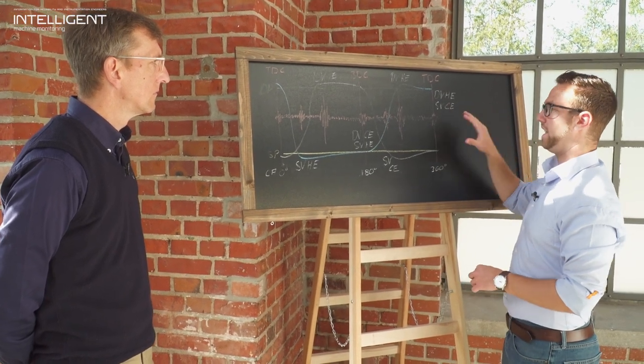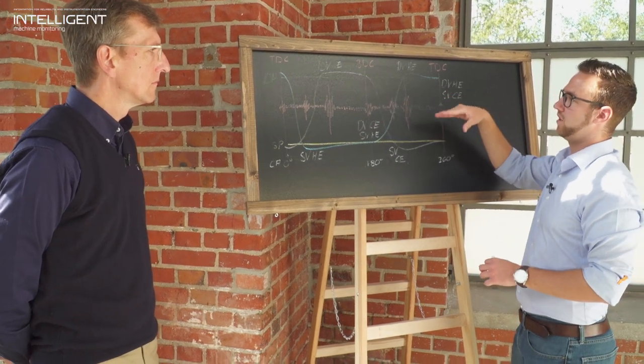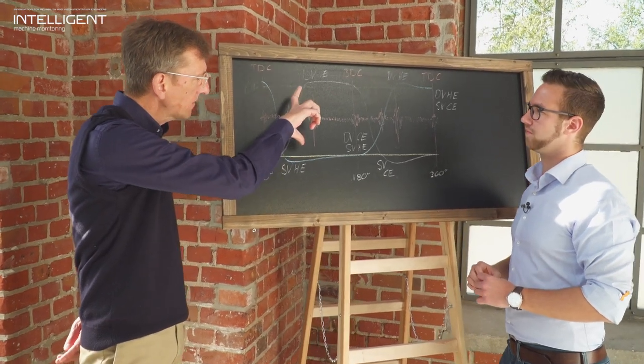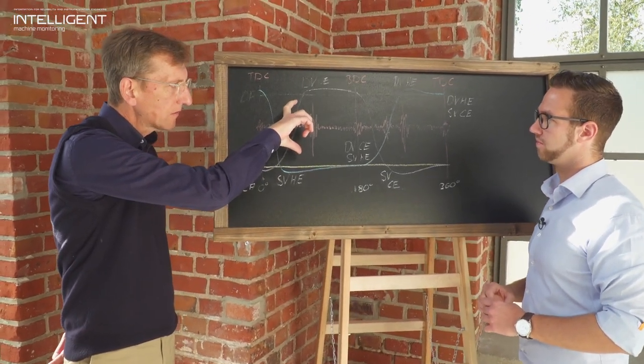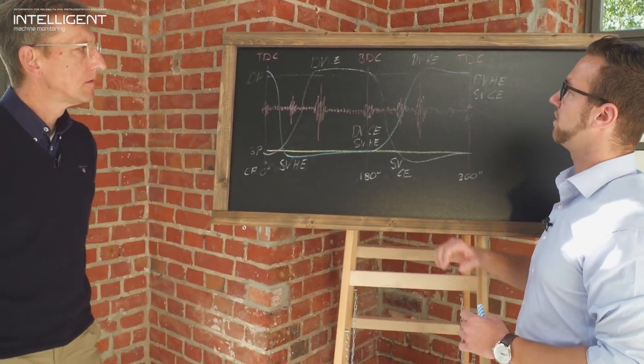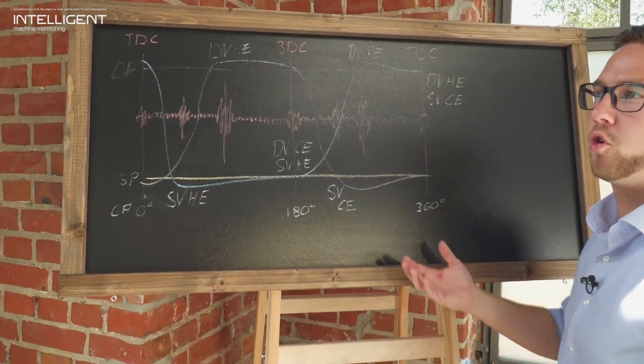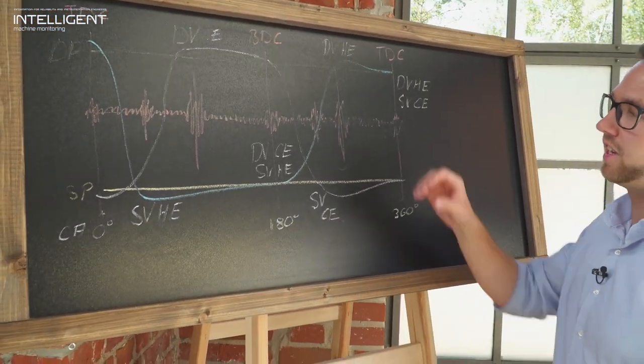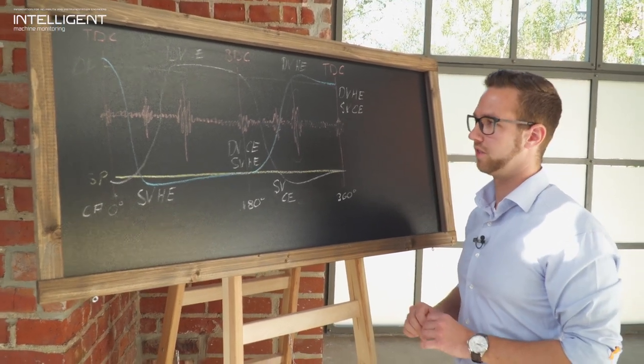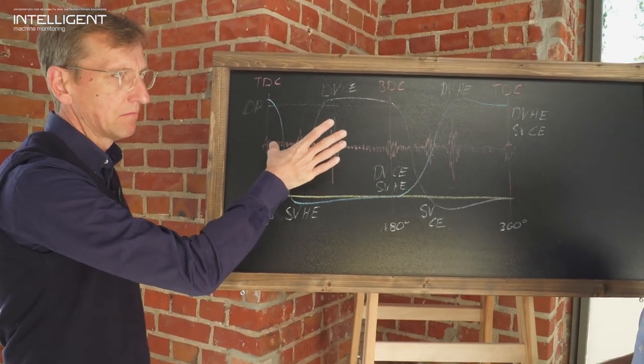So as I understand, the opening phase produces larger peaks than closing? Yeah, that's usually the point because there's a higher pressure level on the opening time, which is having more energy in the system, and that is usually why they're opening harder than closing. So this reading is a good condition, reference values.